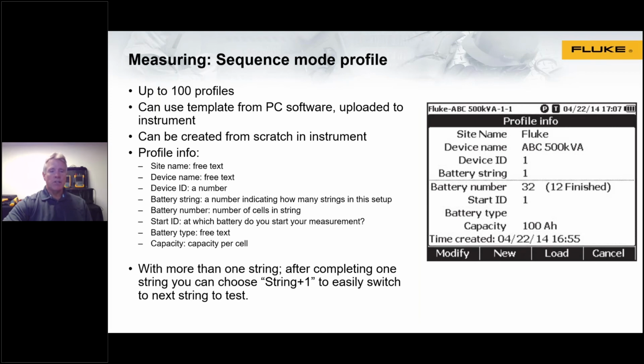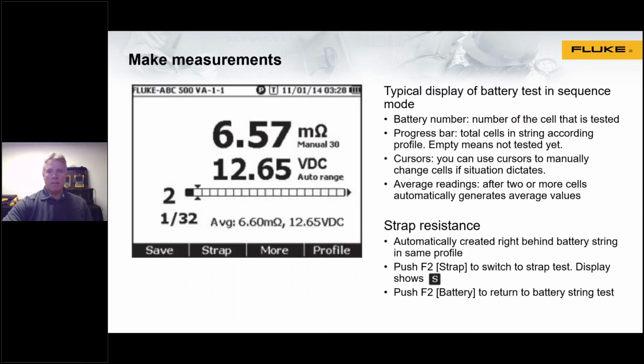And what we'll do on the next slide is take a look at what that might look like when you're using it. There's a sequence button on the battery tester, and then you have the option to load in the sequence name that you want to use, and then as a user, it would start to prompt you through. On the screen you can see what looks like 32 batteries in the string, and it also tells you what battery number you're testing. It looks like we've stored something because it's filled in reverse video in battery number 1. And the cursor has moved to battery number 2, so that's the one we're testing. You can just place the probes on battery number 2. It could be auto-saved or manually saved, and then it would automatically advance.